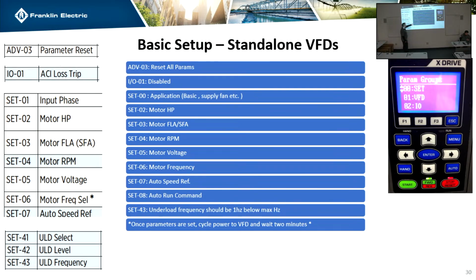Underload is going to be defaulted on. It's for pump and HVAC, but they call them two different things. In pump, they call it dry run. In HVAC, it's like broken belt. Basically, if you have a fan and you can test it, what you want to do is run the motor without the fan physically attached to see what amperage the motor is going to pull. And you can set your underload at 1 hertz below your max frequency. And then you go in and set the underload level to whatever that amperage is that you detected. That way, if the motor ever runs at full speed with that setting, it knows that your belt's broken.